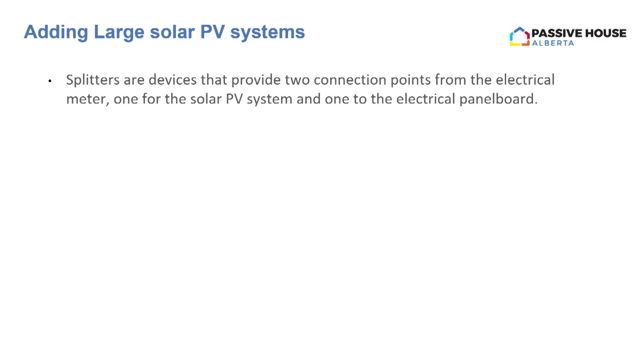So the rating of your panel, that's that number that's on the sticker somewhere on the panel, that's the rating of the bus bar. And that sets, there's again another code calculation, how much solar you can put at the bottom. So you could put in a larger panel with a larger bus bar, but then still use a smaller 100 amp breaker, so that you still only are taking 100 amps from the grid, but it gives you that larger connection to put a larger solar feed at the bottom.